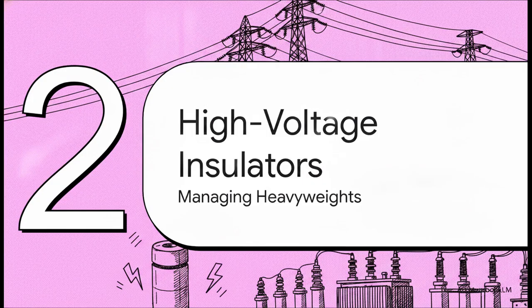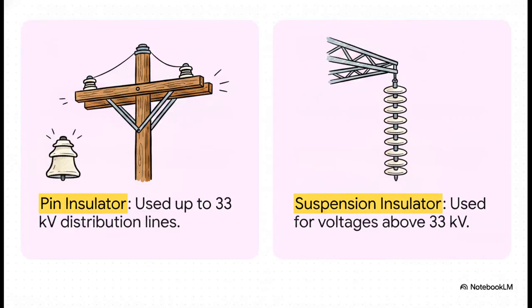Moving on to part two, managing high voltage heavyweights. Let's see exactly how voltage dictates design by comparing two of the most common types you'll see out there: the pin insulator and the suspension insulator. The magic dividing line here is 33 kilovolts. The pin insulator, which has that classic tiered, almost mushroom-like shape, is mounted securely on a pin fixed directly to the crossarm of the pole. It's incredibly effective, but it is strictly used for distribution lines carrying up to 33 kV.